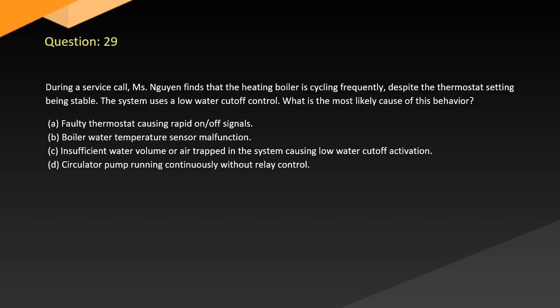Question 29. During a service call, the technician finds that the heating boiler is cycling frequently despite the thermostat setting being stable. The system uses a low water cutoff control. What is the most likely cause of this behavior? A. Faulty thermostat causing rapid on-off signals. B. Boiler water temperature sensor malfunction. C. Insufficient water volume or air trapped in the system causing low water cutoff activation. D. Circulator pump running continuously without relay control.